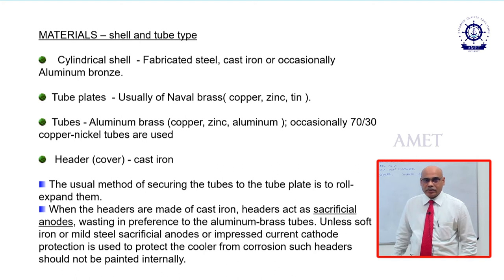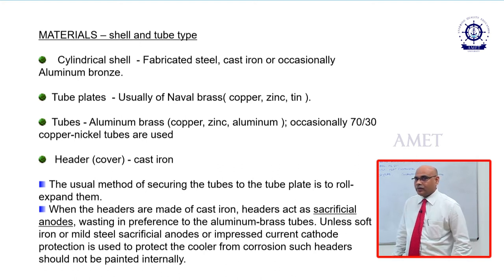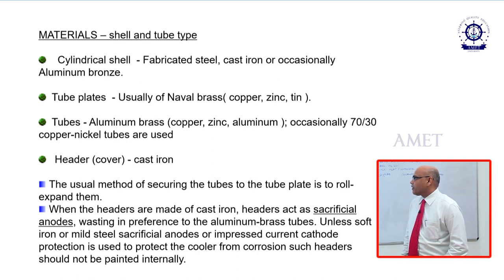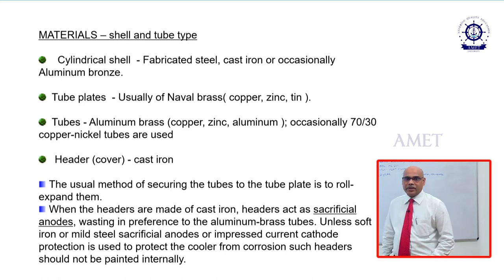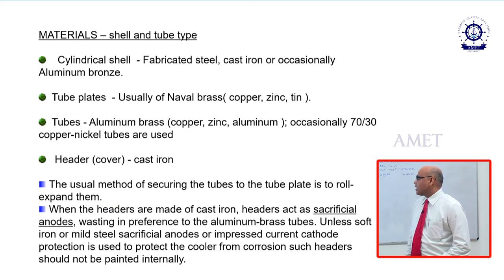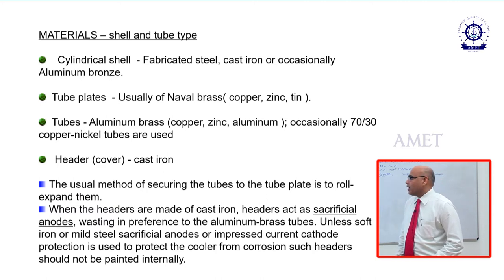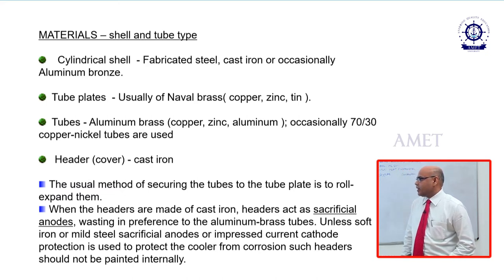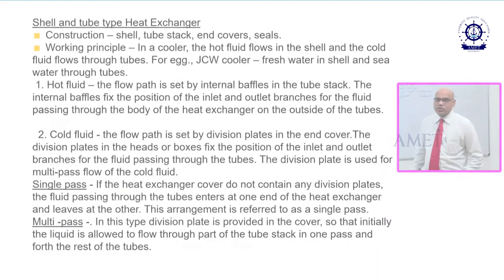Regarding materials: the shell is fabricated of stainless steel, cast fabricated steel, or cast iron. The tube plates are usually naval brass — these are alloys of copper, zinc, and tin. The tubes are aluminum brass, and the head cover is made up of cast iron.